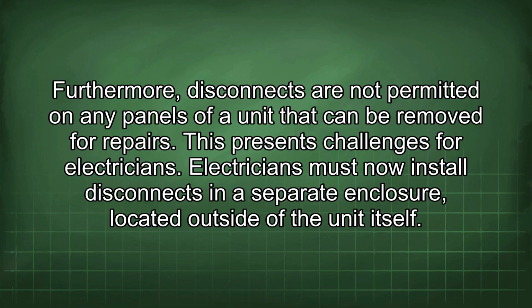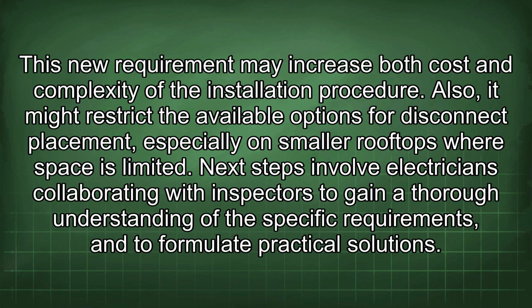This presents challenges for electricians. Electricians must now install disconnects in a separate enclosure located outside of the unit itself. This new requirement may increase both cost and complexity of the installation procedure. Also, it might restrict the available options for disconnect placement, especially on smaller rooftops where space is limited.